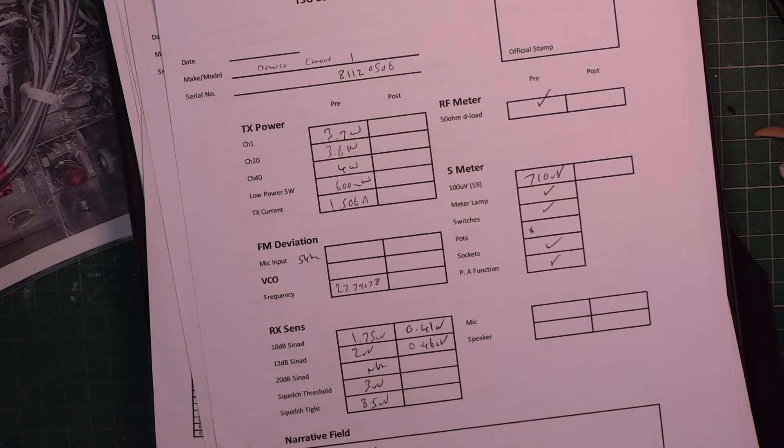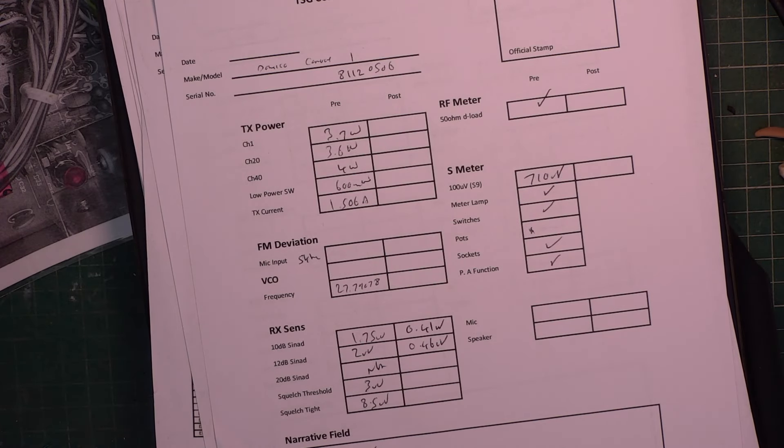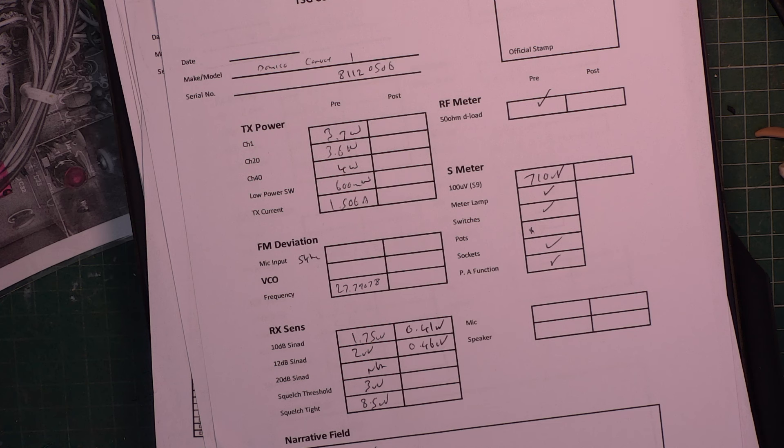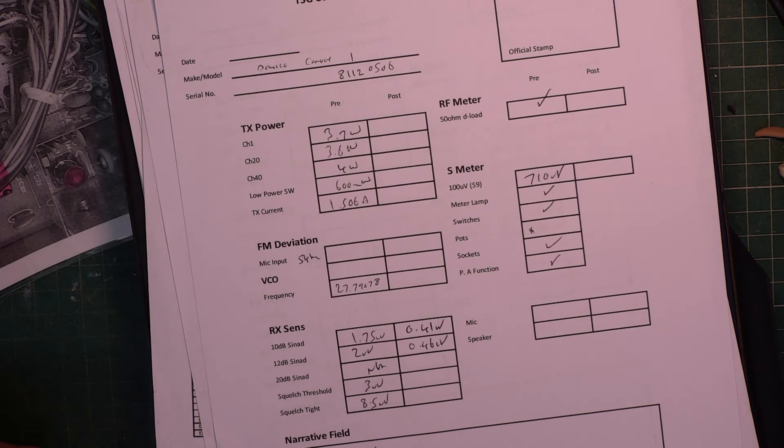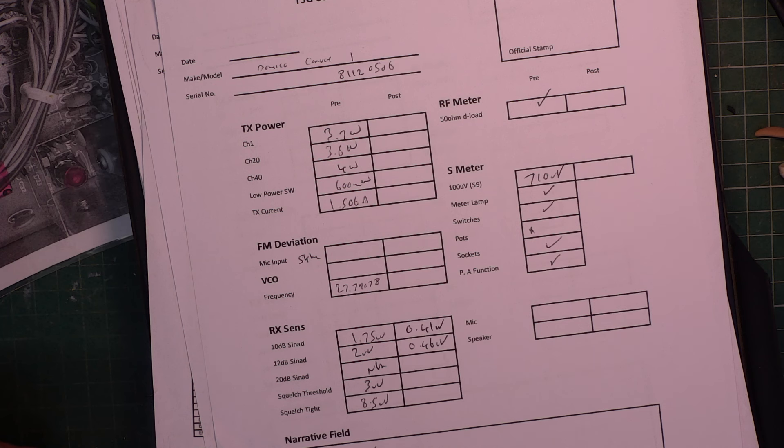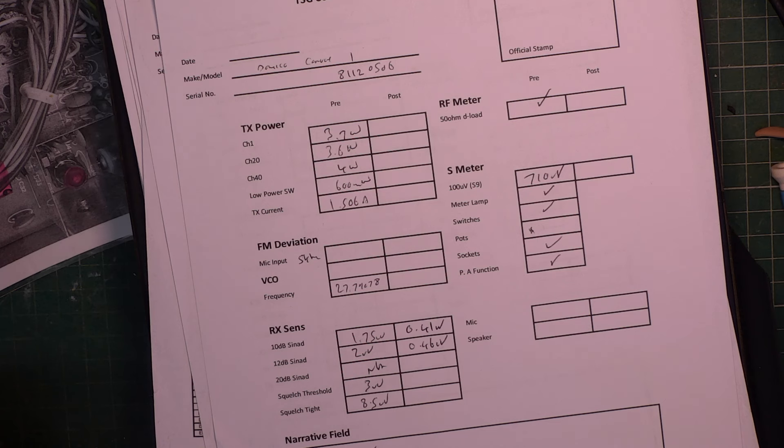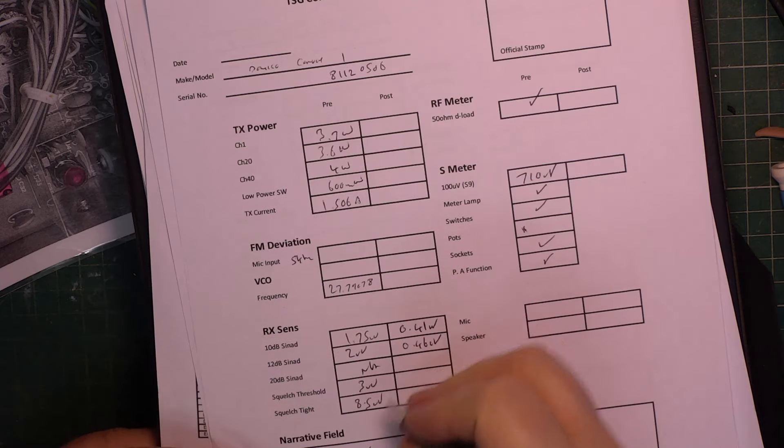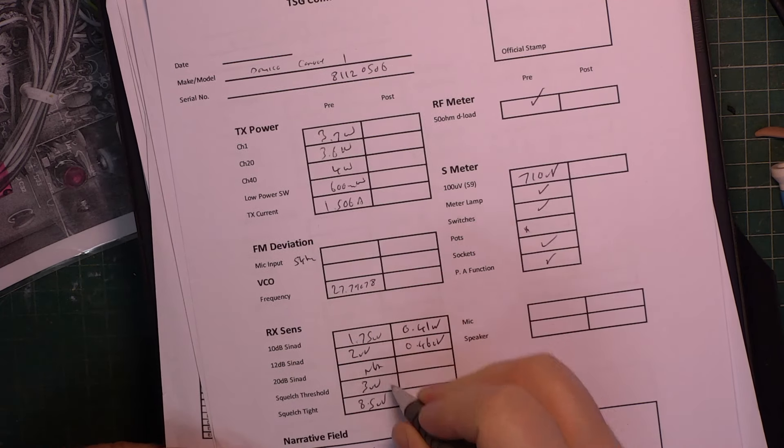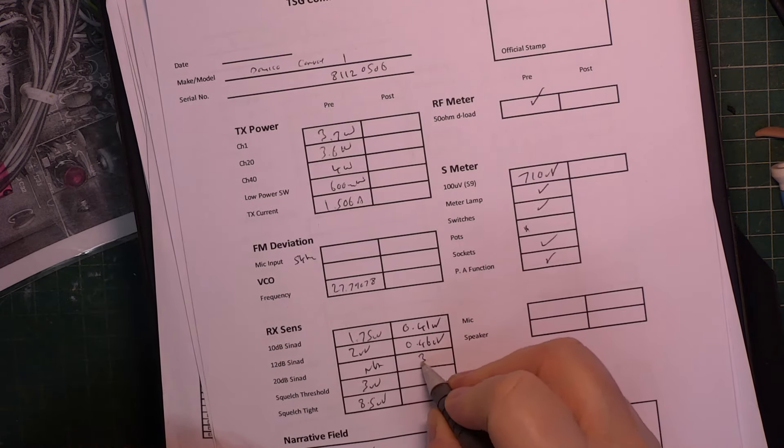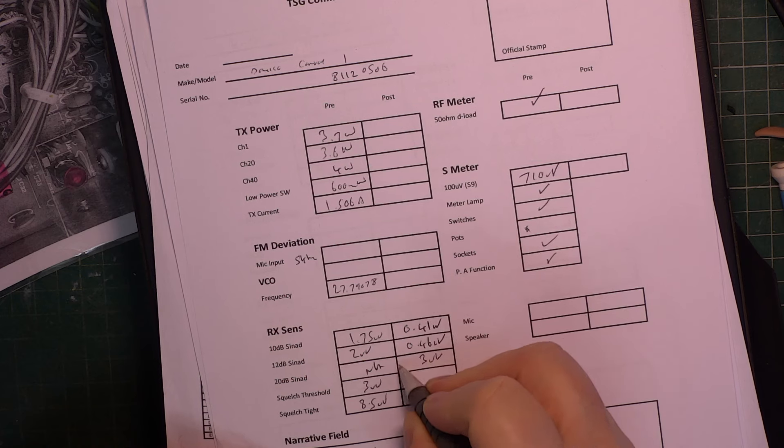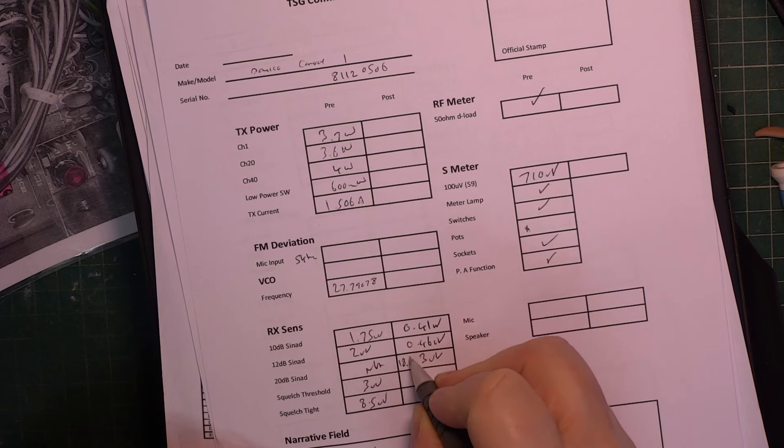Right, let's see what we've got now because it may have altered. 0.5, we'll read 0.5 there. 0.41. No, it's never going to do 20. It's just noise, that. It's going to do 18. 3 microvolts. Well it didn't before. So 3 microvolts, 18 dB.